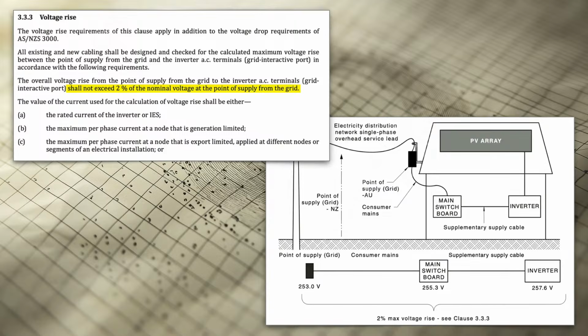And the voltage rise is most extreme within the installation, within the electrical installation. So keeping that to less than 2% is the requirement of the standard. How do you determine that? Well, it's really Ohm's law, the size of the cable and the length of the cable.